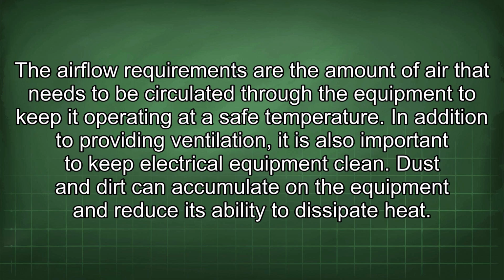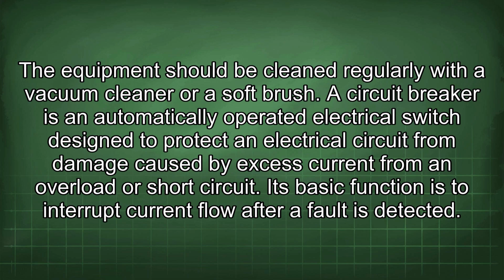In addition to providing ventilation, it is also important to keep electrical equipment clean. Dust and dirt can accumulate on the equipment and reduce its ability to dissipate heat. The equipment should be cleaned regularly with a vacuum cleaner or a soft brush.